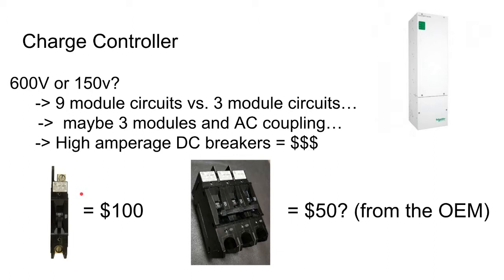When I made this design mistake and shot from the hip, we had 3 charge controllers, and I ordered 3 80 amp breakers when they really needed to be 3 100 amp breakers. As soon as those breakers started to trip, I realized we were getting up to our maximum rated capacity, and I needed to swap out these breakers for the system to function as sold.